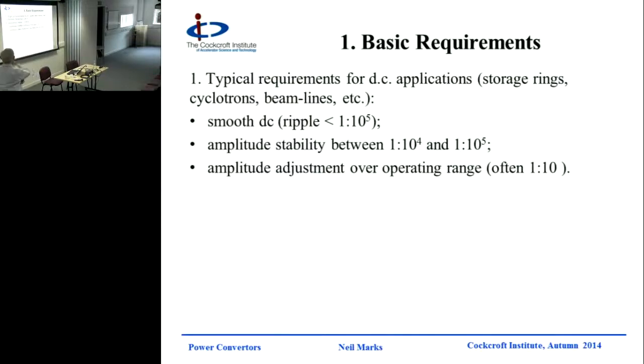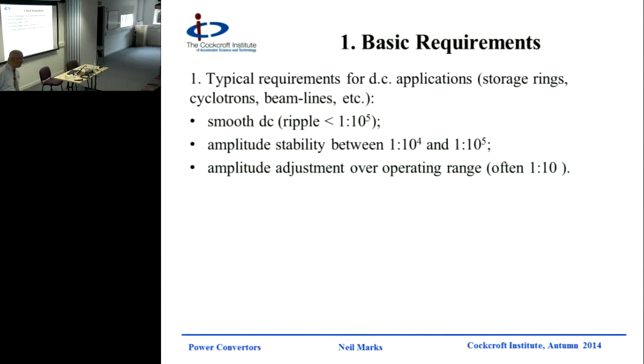So what do we basically need for the DC application? This would be storage rings, cyclotrons, synchrotrons, the whole lot. We need smooth DC - ripple variations better than one part in 10 to the 5. Amplitude stability: you don't want the things bouncing up and down all the time, between one part in 10 to the 4 and one part in 10 to the 5. And then we need to be able to adjust the amplitude - from the controller with a knob, or more likely with the computer these days - with a resolution of the order of one part in 10 to the 5, over a range of at least one in 10, if not more.